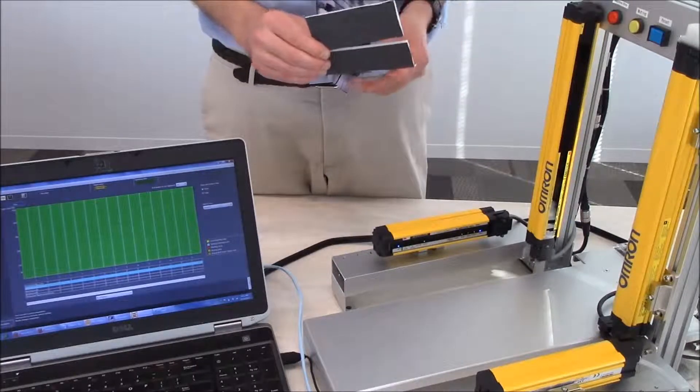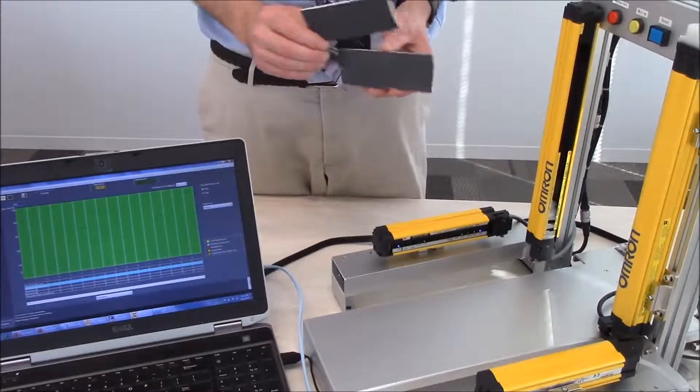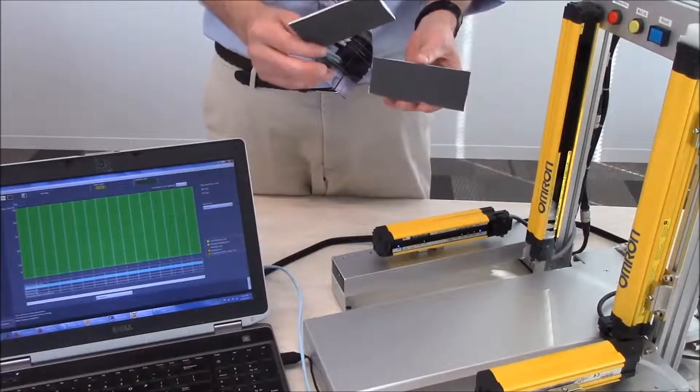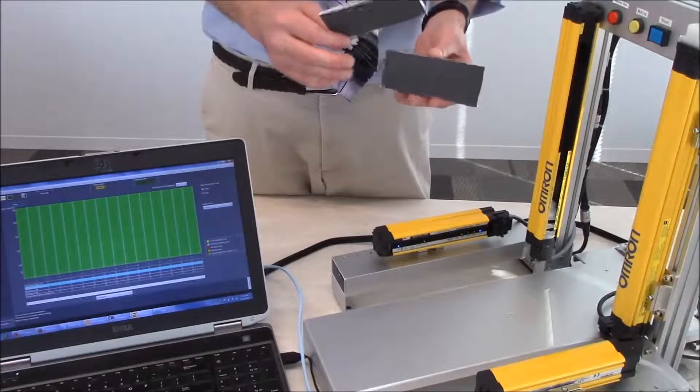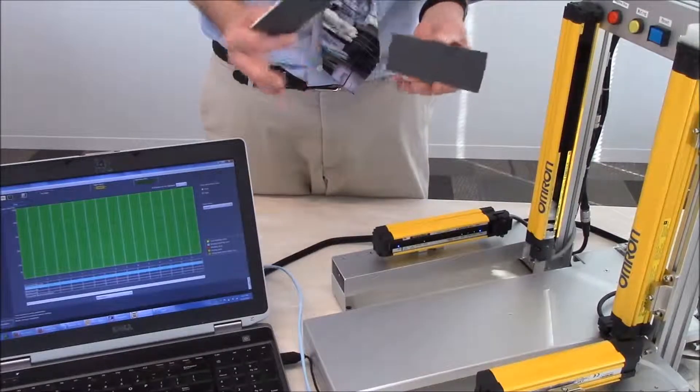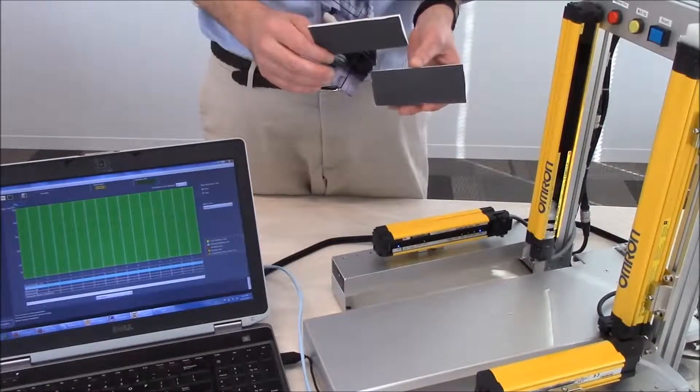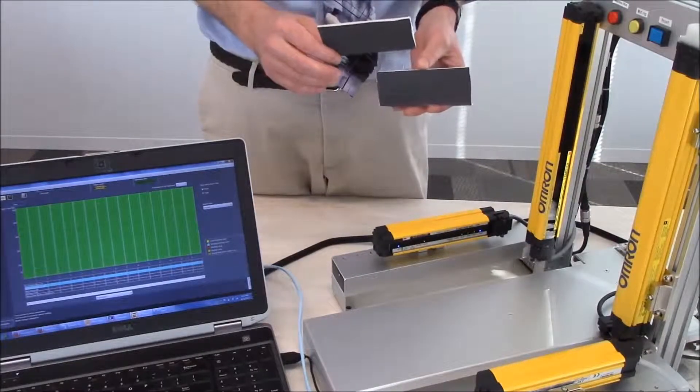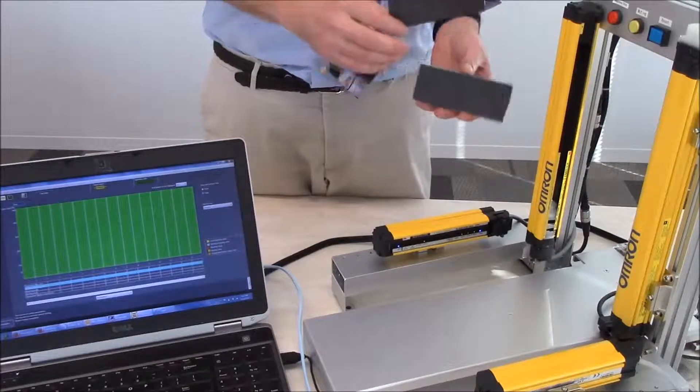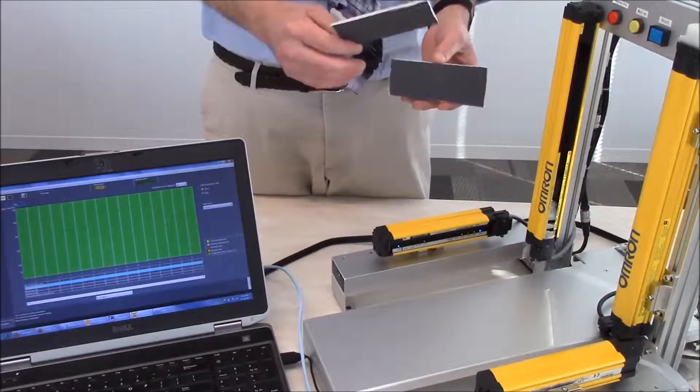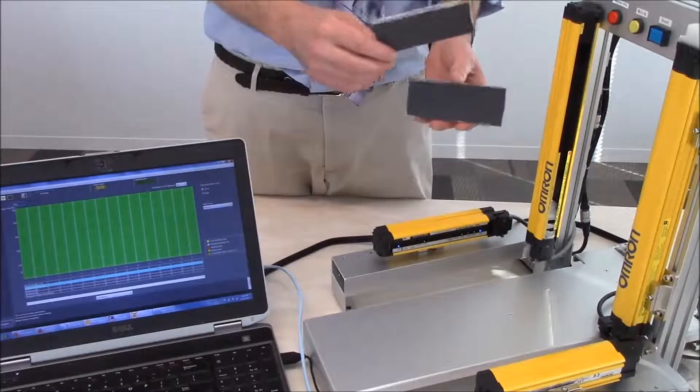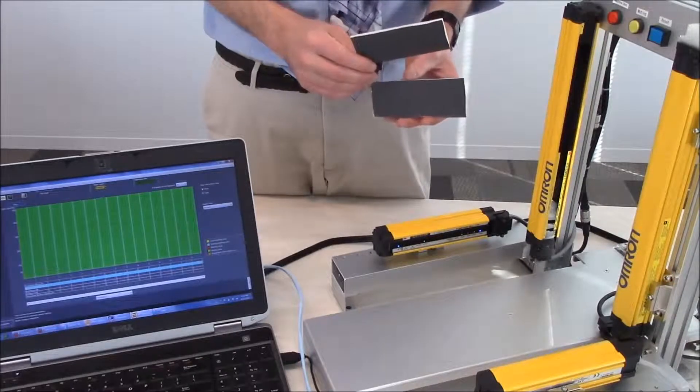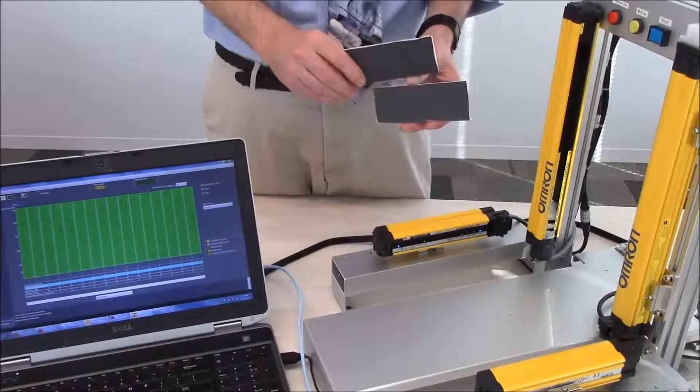As long as you don't exceed the number three, in this case the way that we had set it up in this presentation, as long as you don't exceed three beams you should be able to put objects into the light curtain area without tripping the light curtain.